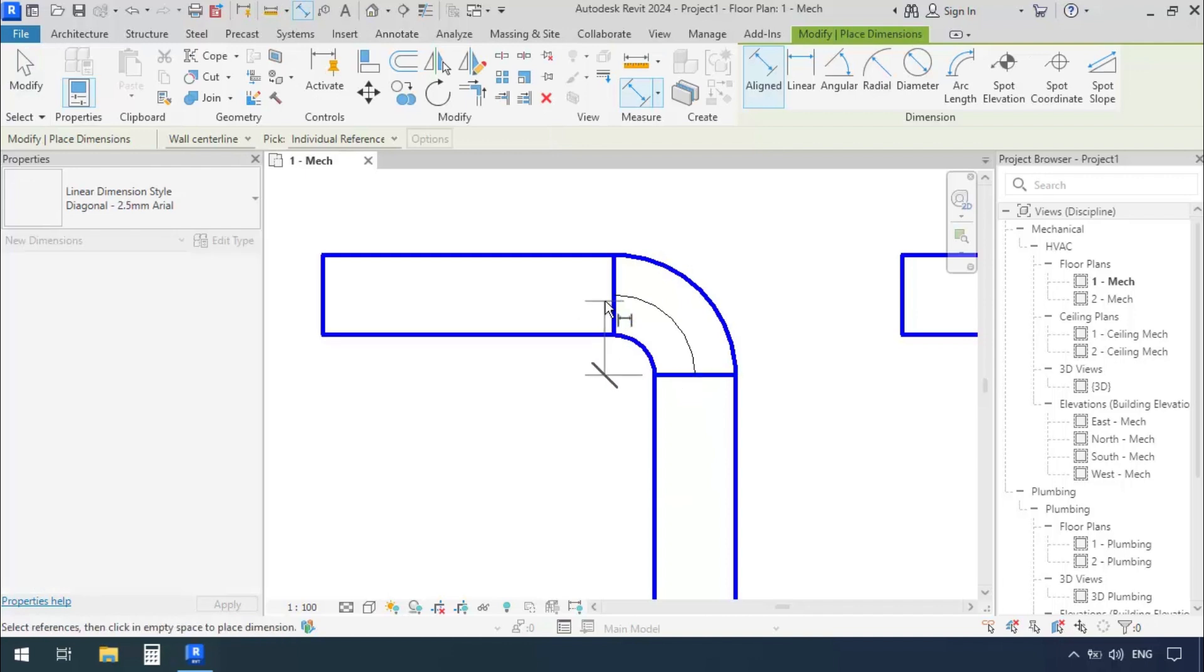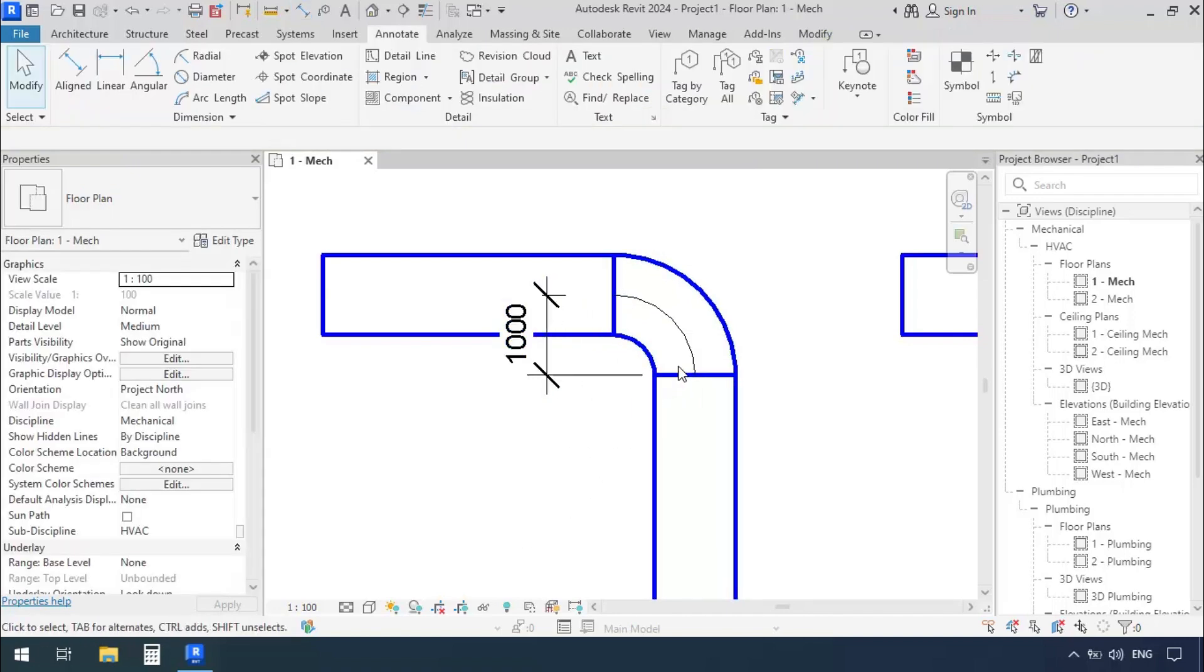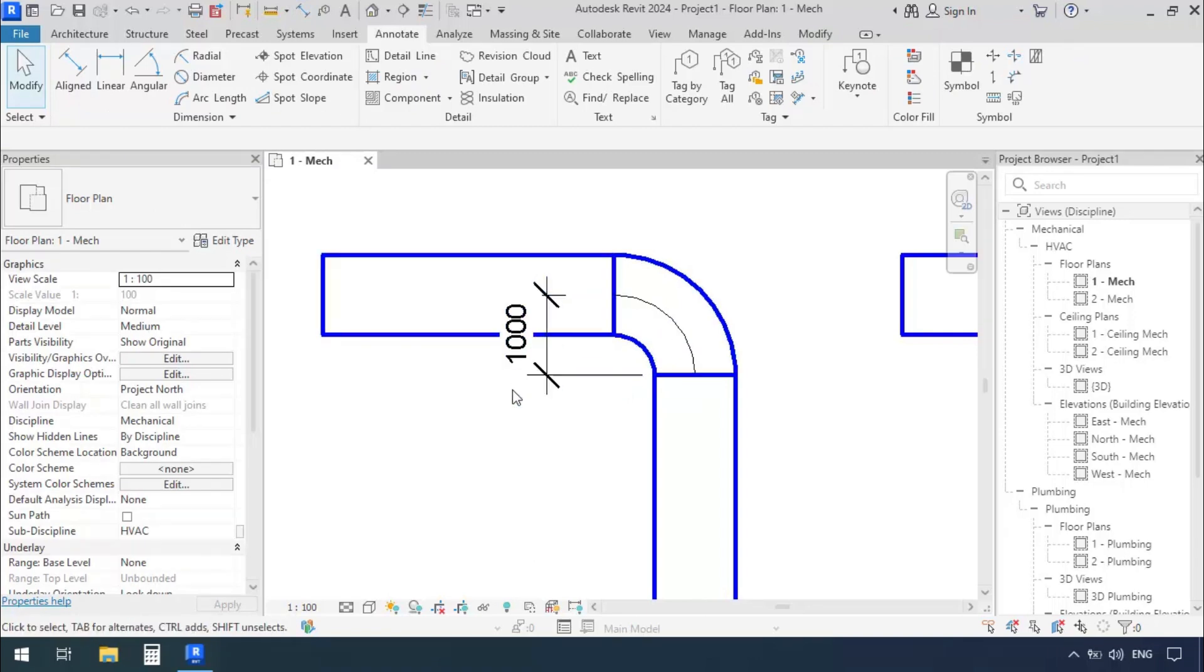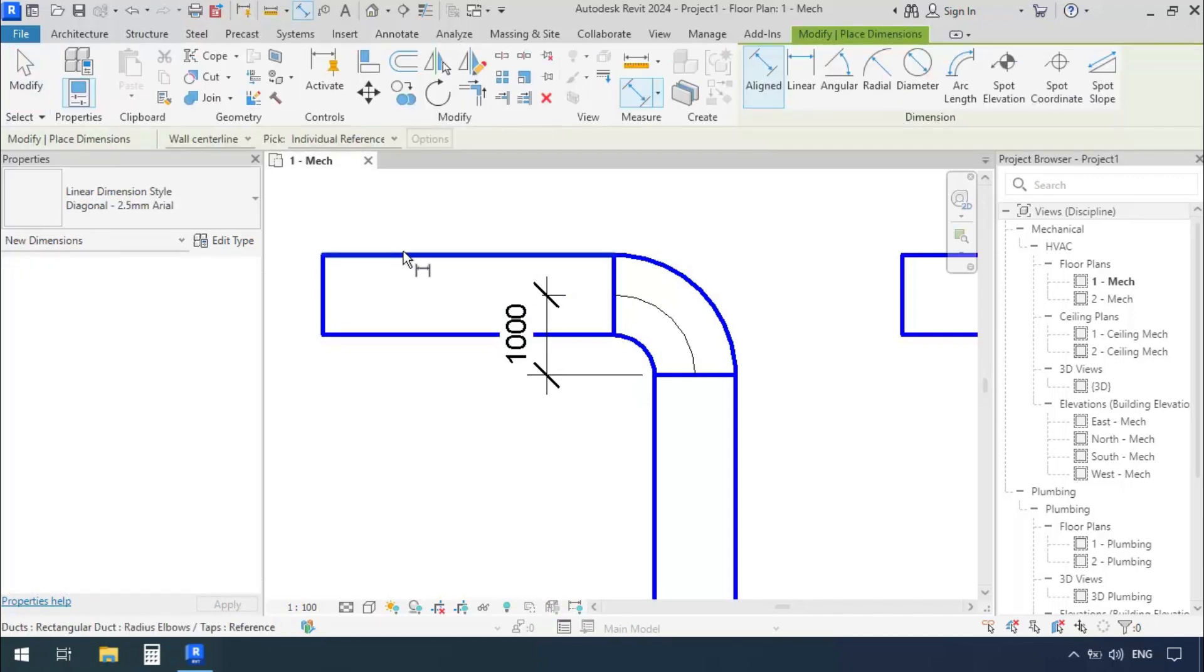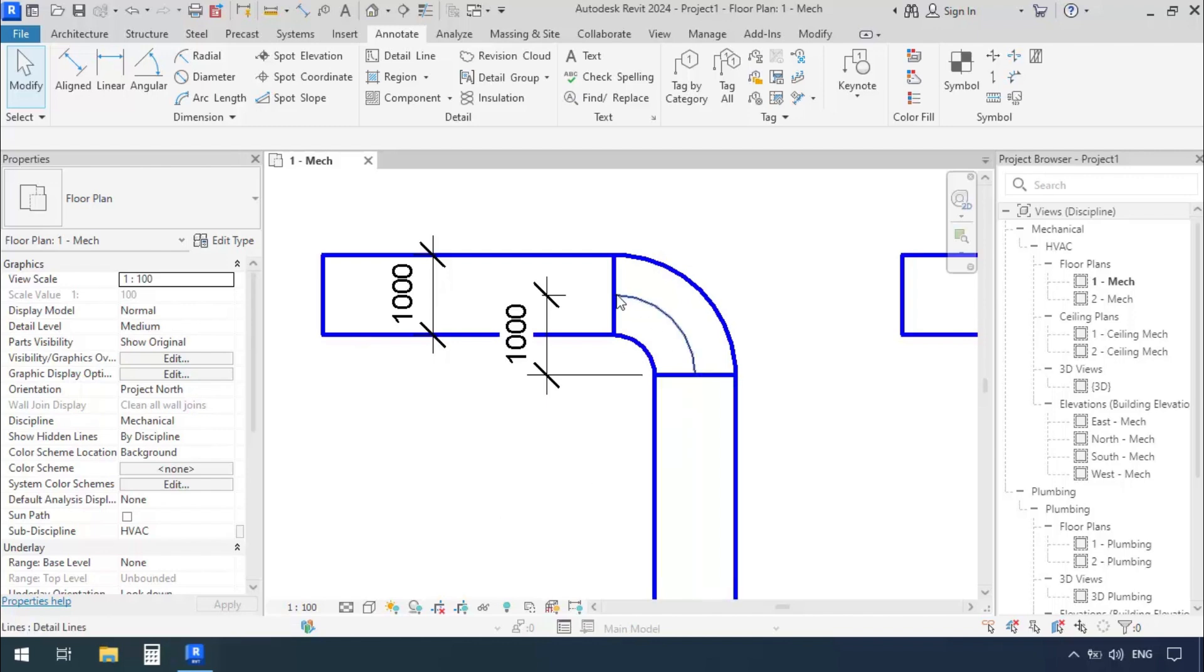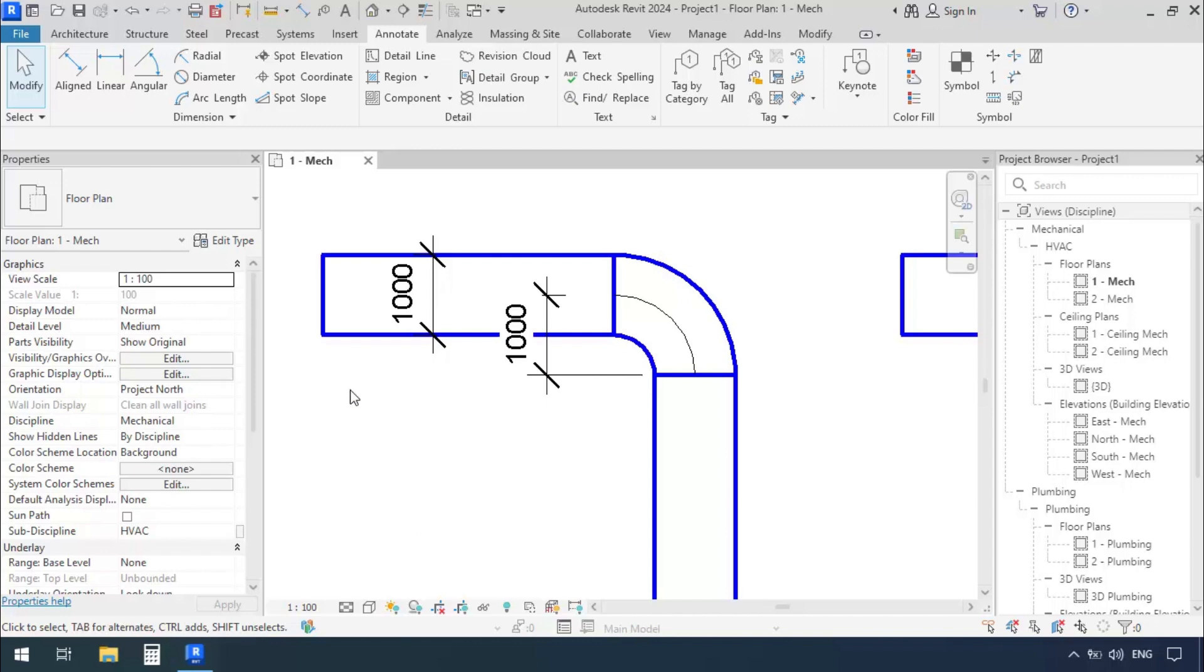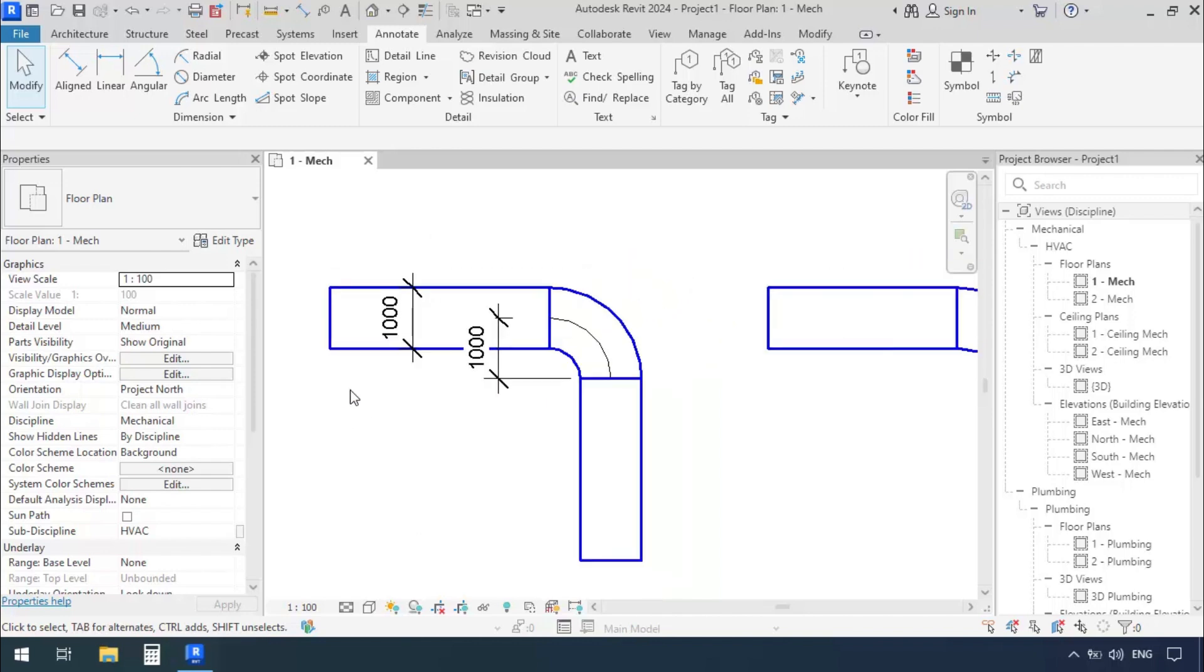Now we want to measure this radius. I'll click on Align Dimension Command. First click here, then in the middle of the duct we'll make the second click. Then click somewhere empty. We use these lines to figure out the radius of this arc. We have the number 1000. The width of our duct was also 1000. The widths of ducts are referred to as W in short. If we divide the radius by the width, 1000 divided by 1000, we conclude that the radius of the elbow is one time the width or W.